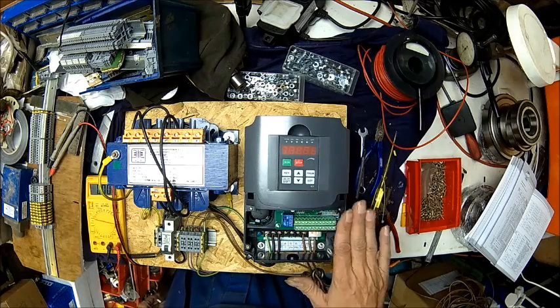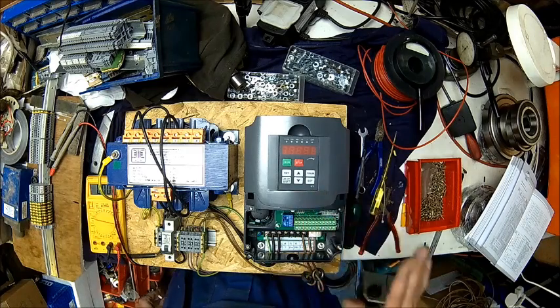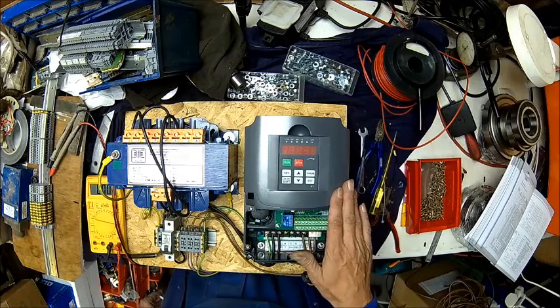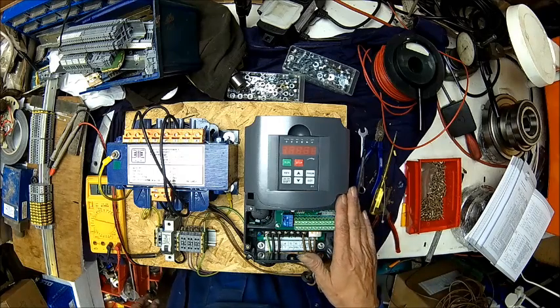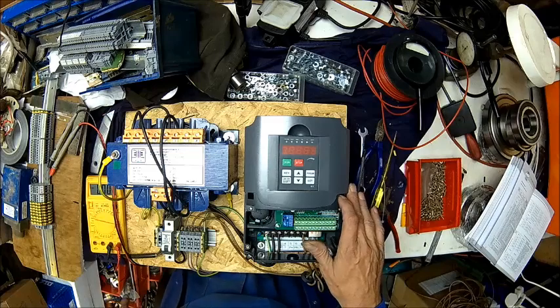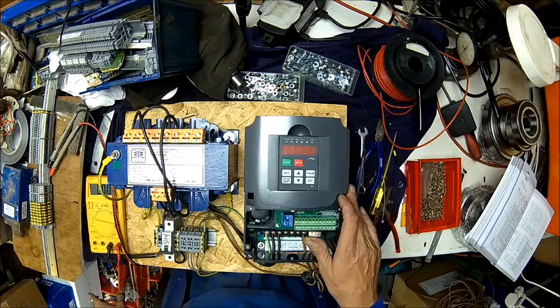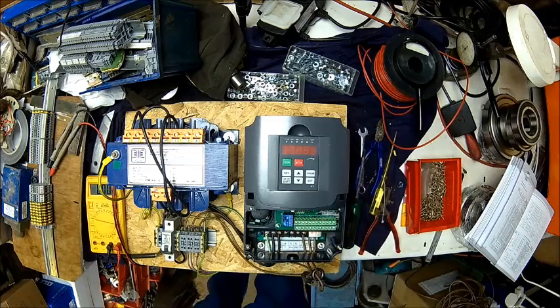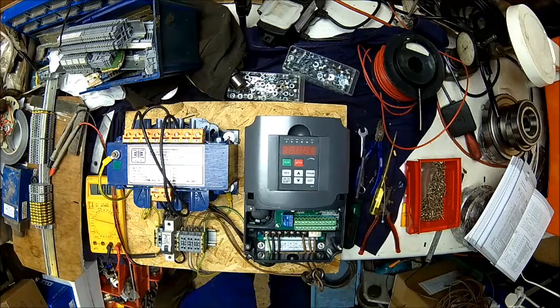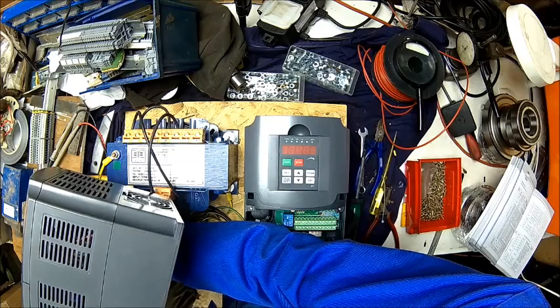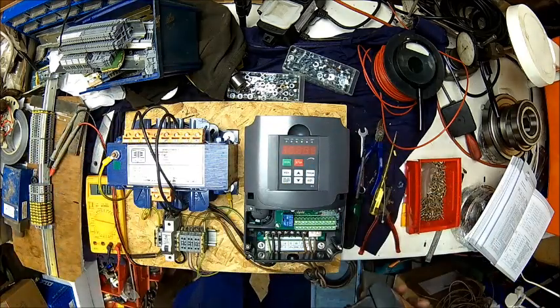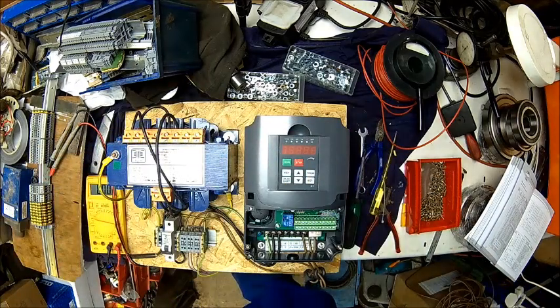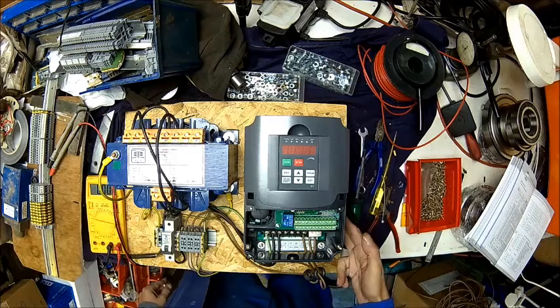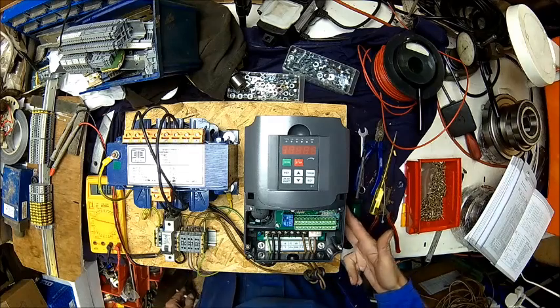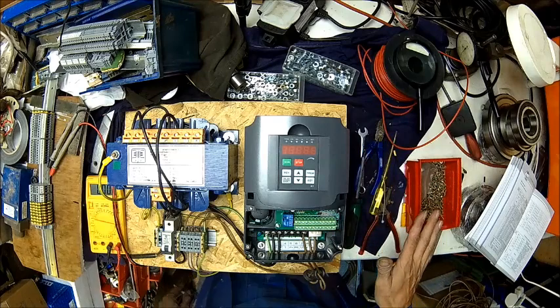But the main thing which costs you money is the current. If you buy a 4 kilowatt inverter for 230 volts, it's actually a higher current rating. If you look at the other one I have here, this thing says 18 amps at 230 volts. This one says 8.5 amps or 9 amps at 400 volts. Both 4 kilowatts, because power.